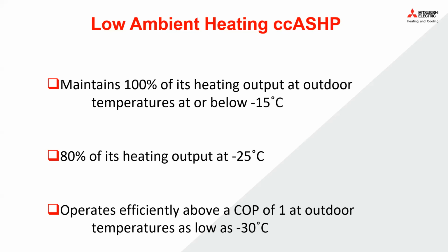So as a company, we're constantly striving to gain further cold weather performance. The bulk of our product right now maintains 100% of its heating capacity at negative 15, and it provides 80% of its capacity at negative 25. And we still generally have a COP above one at temperatures as low as negative 30 for our cold climate systems.